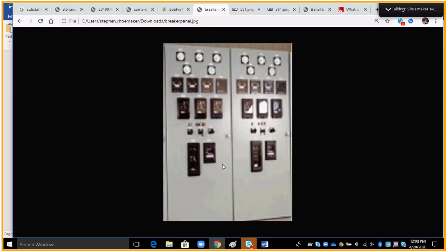All right. What's going to happen here, and this actually happens with motors inside. When I have SCADA, and I call SCADA and I say I need a hotline work permit on this circuit, remember, it turns off the reclosing relay. A little motor behind the handle here turns it to the left. A red flag will come up. They've actually got a red light right here that lights up, and it will actually turn it off. So that happens there, and that's a requirement.